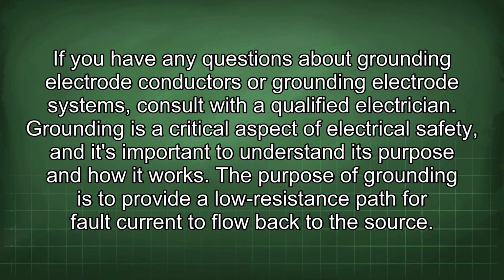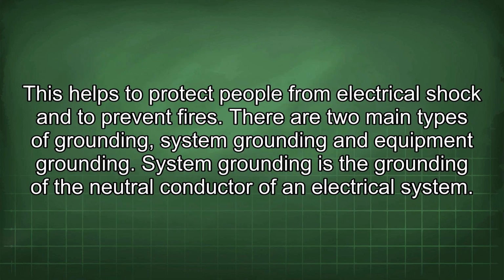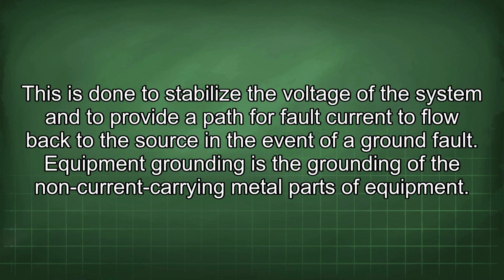Grounding is a critical aspect of electrical safety, and it's important to understand its purpose and how it works. The purpose of grounding is to provide a low resistance path for fault current to flow back to the source. This helps to protect people from electrical shock and to prevent fires. There are two main types of grounding: system grounding and equipment grounding. System grounding is the grounding of the neutral conductor of an electrical system. This is done to stabilize the voltage of the system and to provide a path for fault current to flow back to the source in the event of a ground fault.